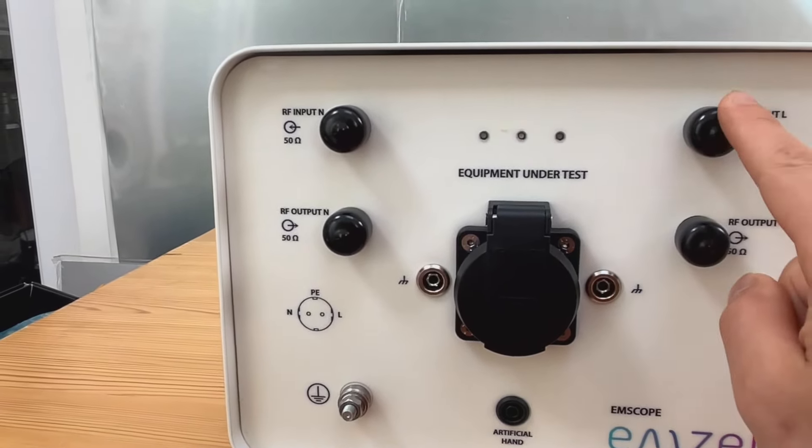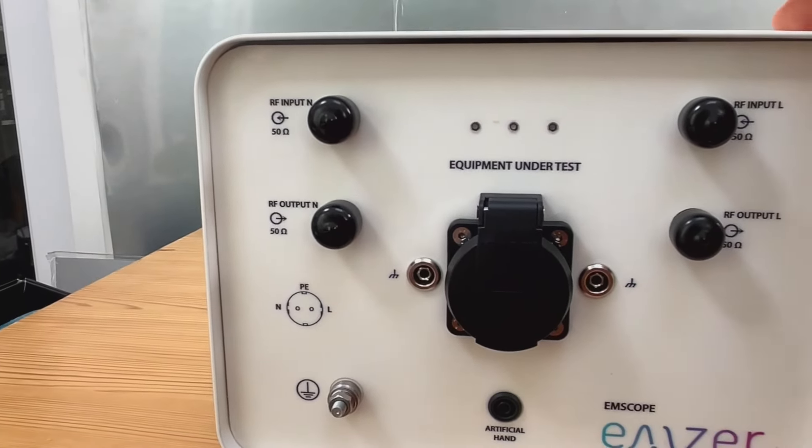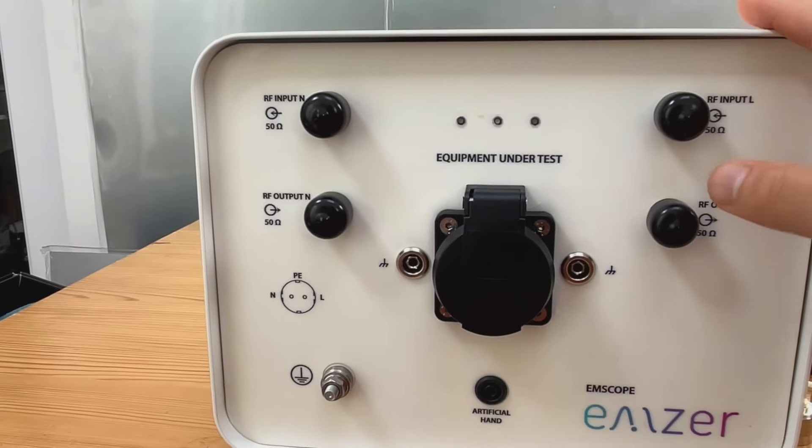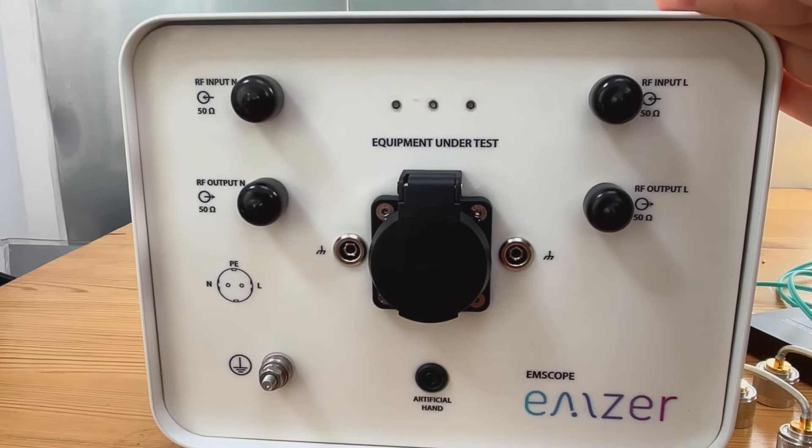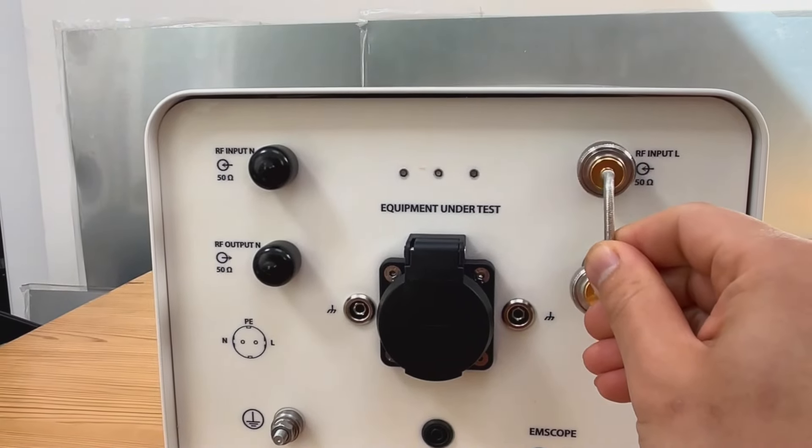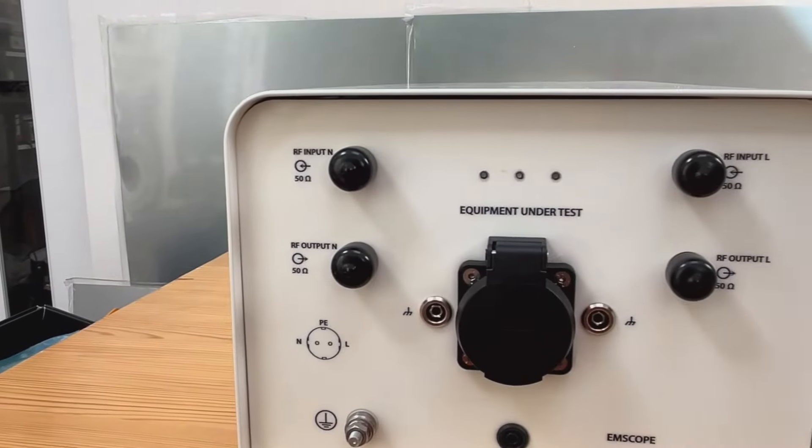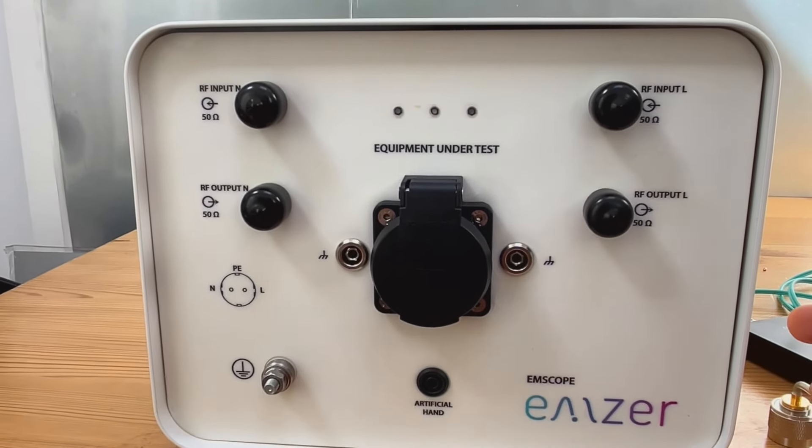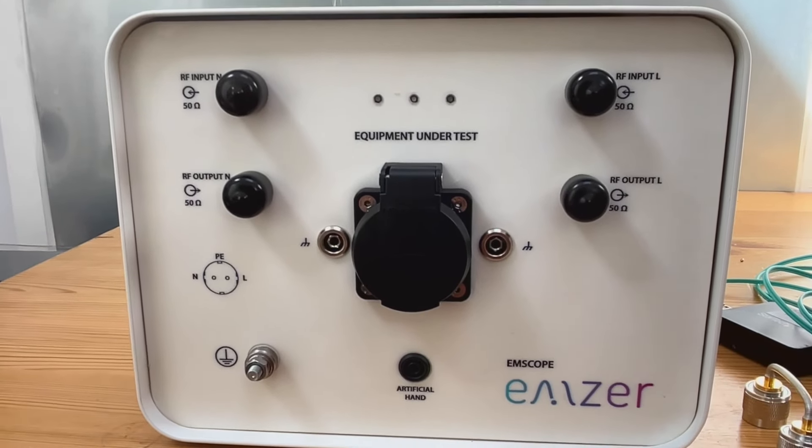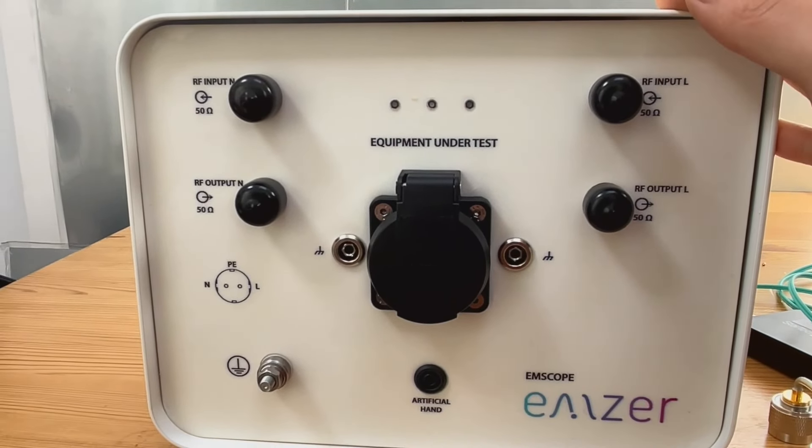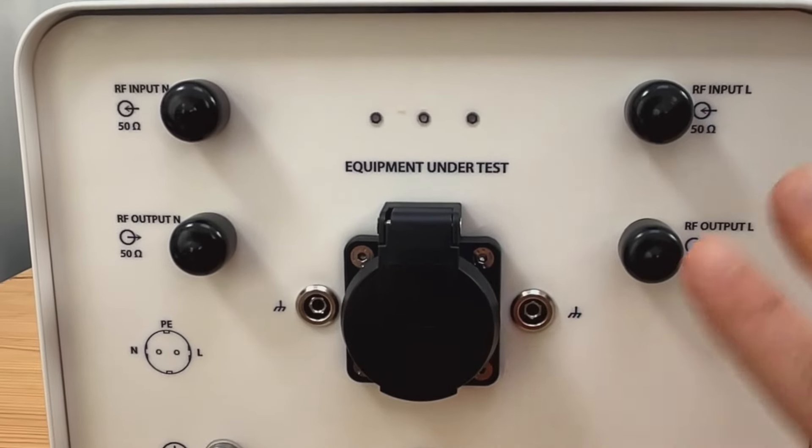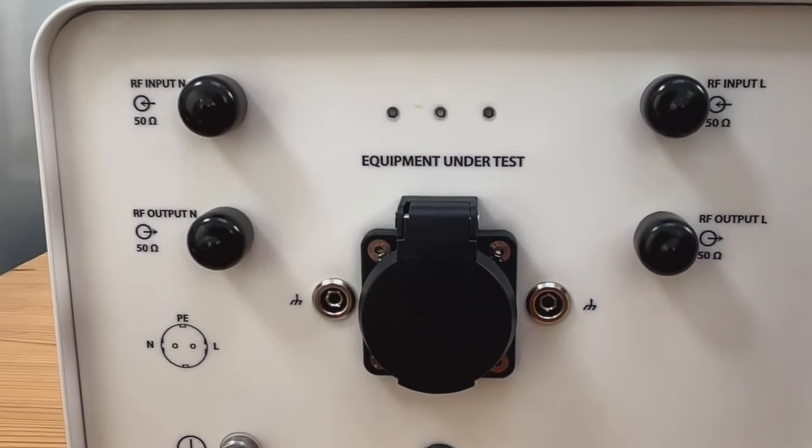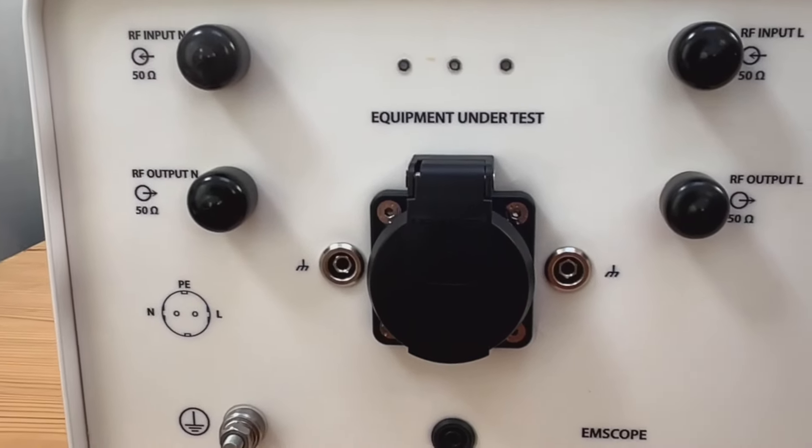Here you got RF input and RF output. Because we mentioned there's a LISN inside, normally if you're using this for conducting emission tests for home appliance application, then you simply link these two using the coaxial cable they provide. However, they also have the version that you can extend the frequency band up to 110 megahertz. That means this can also be used for military defense or automotive application. In that case you have to have your own DC LISN set up, and then the RF inputs can be connected to your own LISN set up.